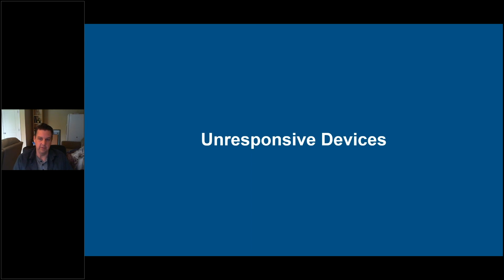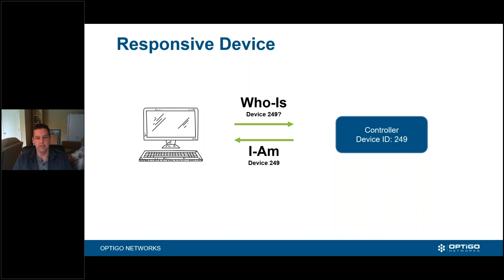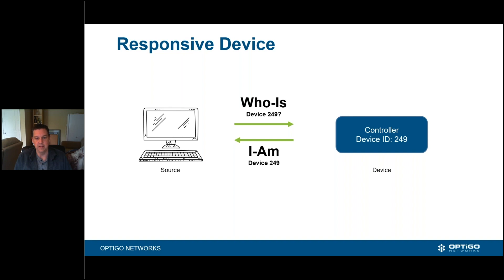An unresponsive device is quite varying — there are a lot of different ways that this can show up and be a problem. A responsive device on your network is quite simple. Something asks a question — a who-is, which could be a full broadcast or specific — and it's expecting a response from a device out in the network. In this particular case, we send who is device 249, and device 249 responds back saying it's the device you asked for. The source might be your front-end BMS system or another device.